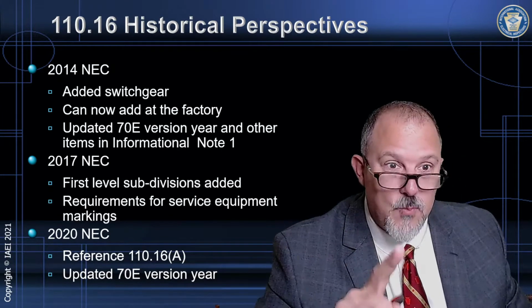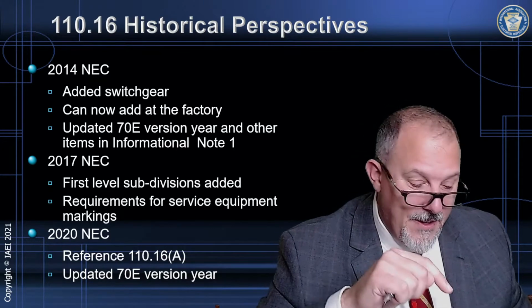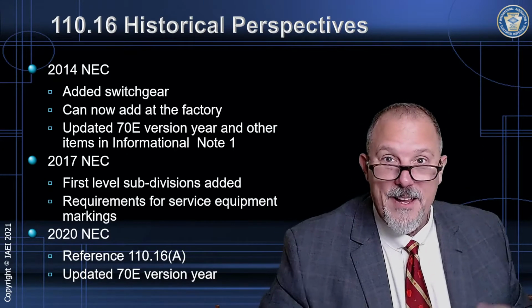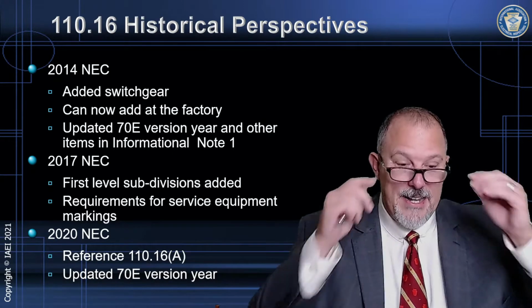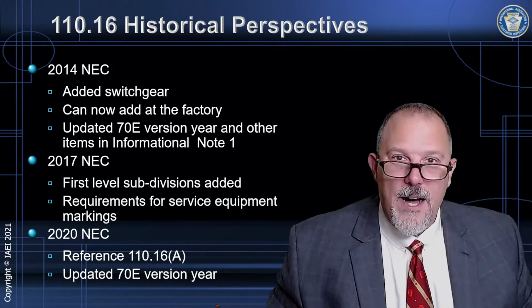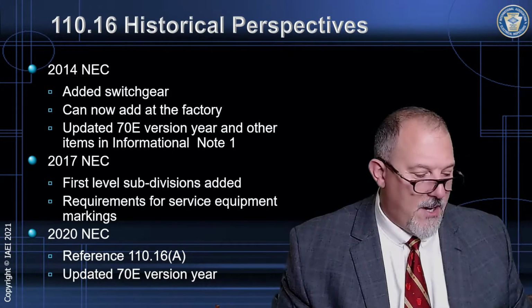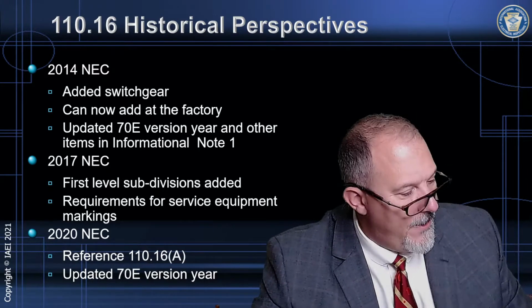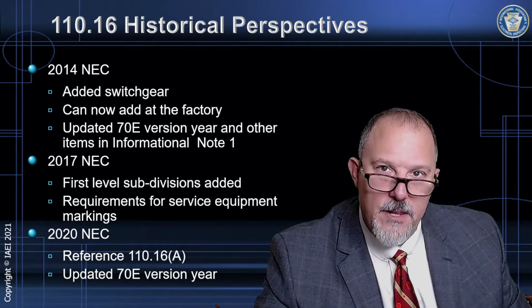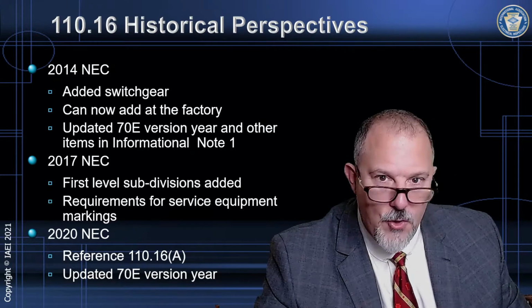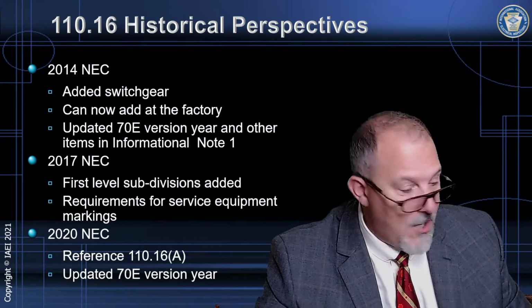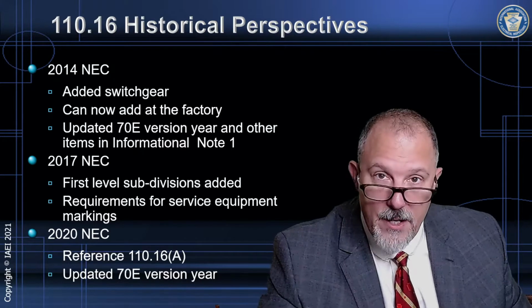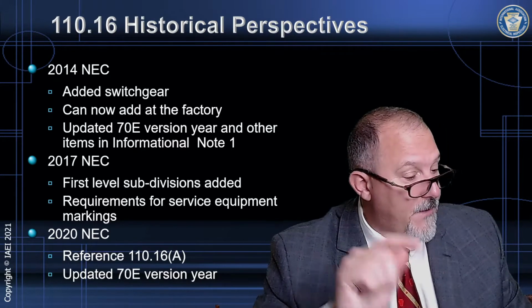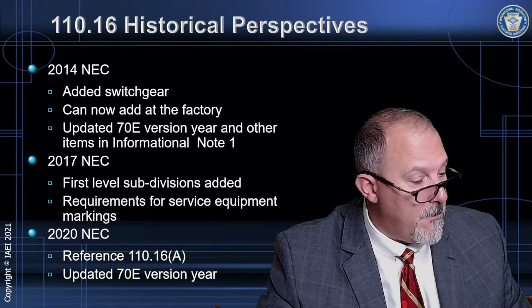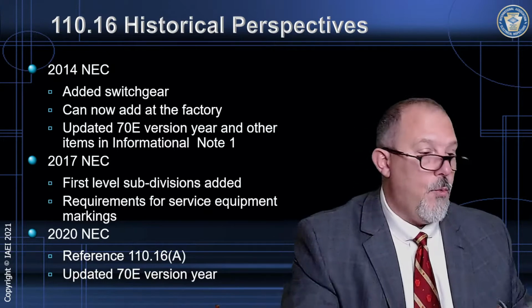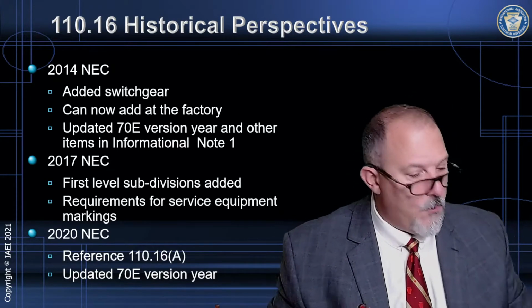And this was the year. This was the breaking point. It was 2014 that said, look, why do we have to scrape these labels off that the factories keep putting on? Why can't we just let them put it on in the factory? And now you have the permission to do that. So now we require it, but it's permitted to be put on in the factory. So field or factory marked. And also, we put a reference to 110.21(B).